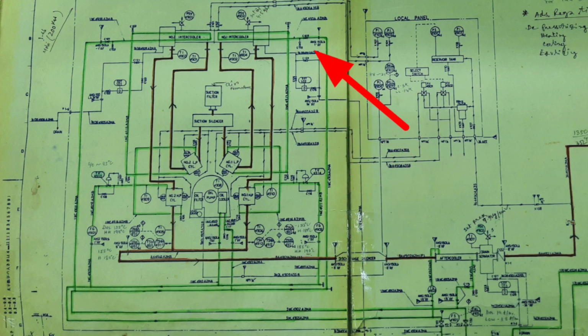Like this way the cooling water will go to the number 1 intercooler, and it will come out and go to the number 1 LP cylinder, and again the number 2 LP cylinder, again discharged by this control valve, and finally it will come out from here. An oil cooler is also available. In the oil cooler, cooling water goes this way and comes out, and finally it goes to the cooling tower system. So by this way cooling water is provided in this compressor house.